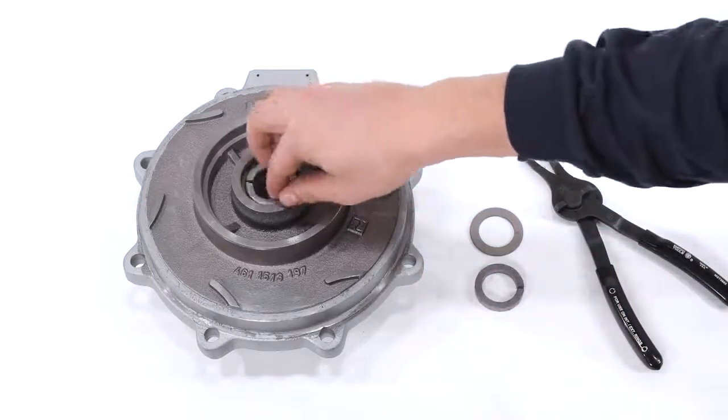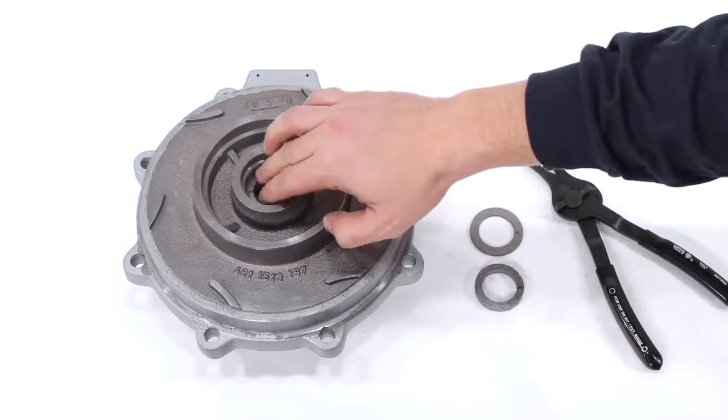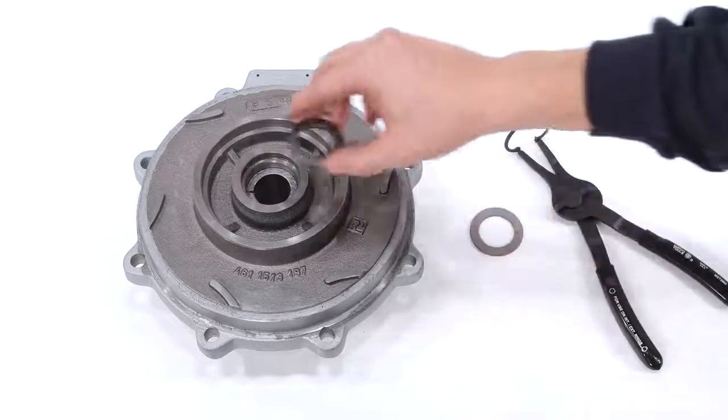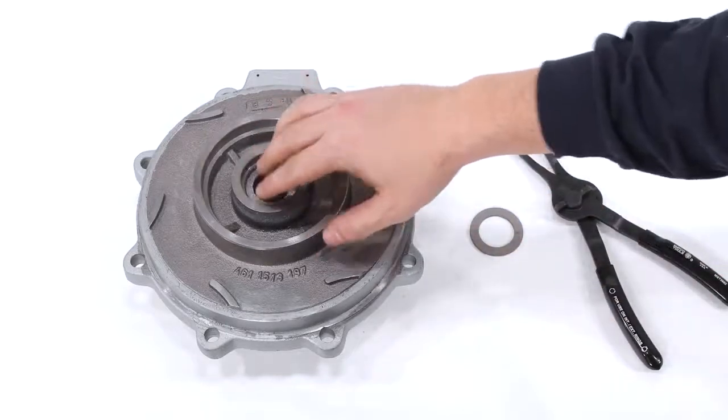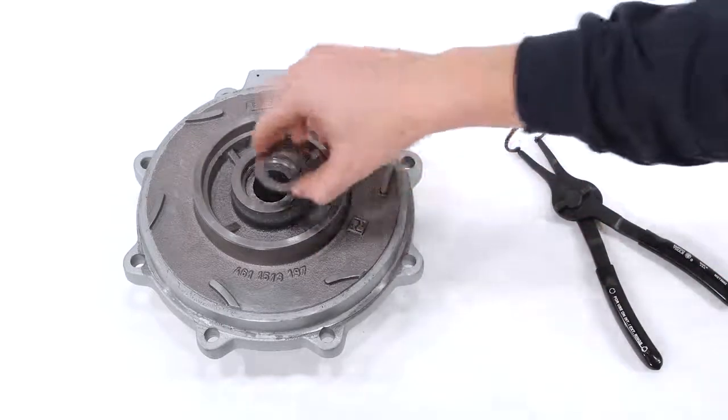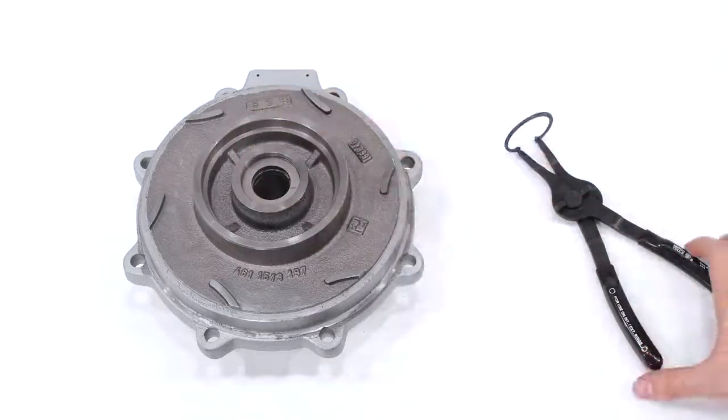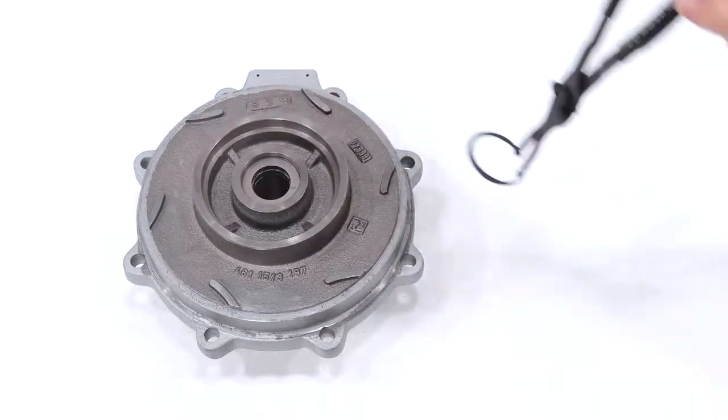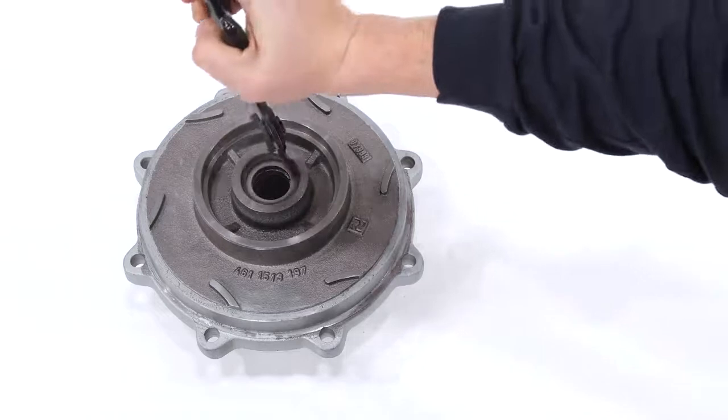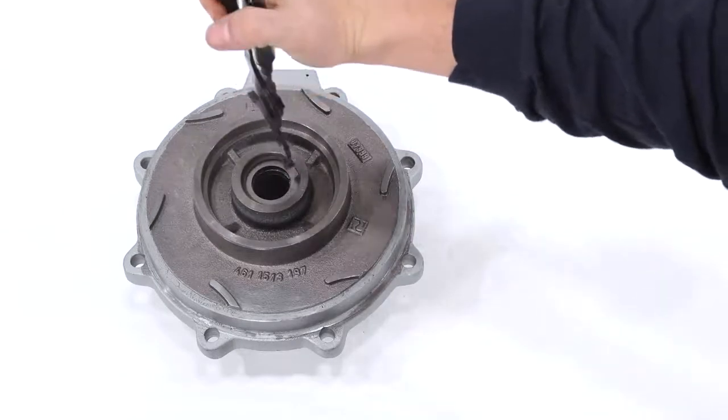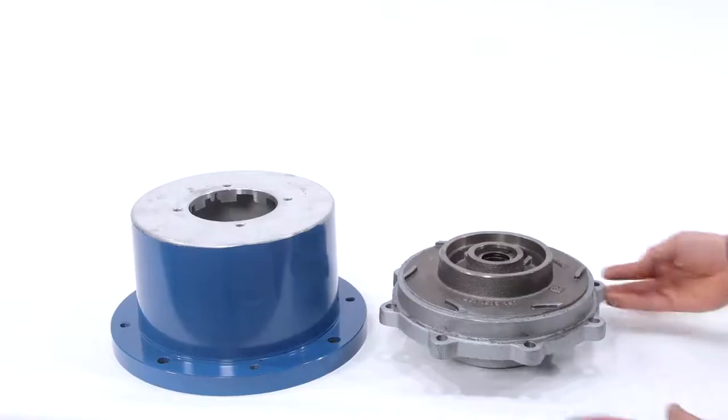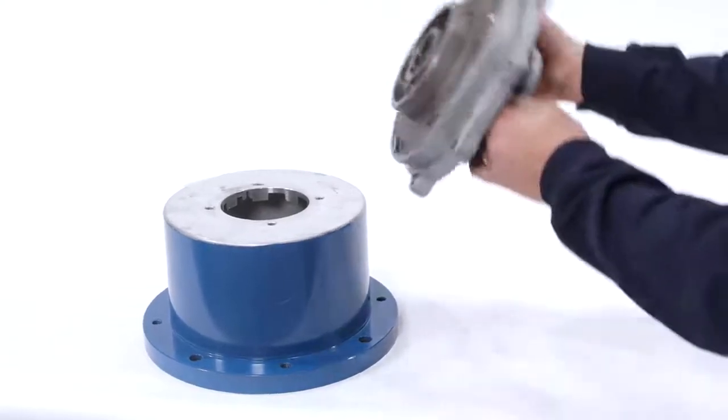Install two packing rings into the stuffing box of the casing cover, making sure the cuts in the packing are opposite each other. Next, install the spacer followed by the snap ring. Place the pump cover on a stand to prepare it for installation.